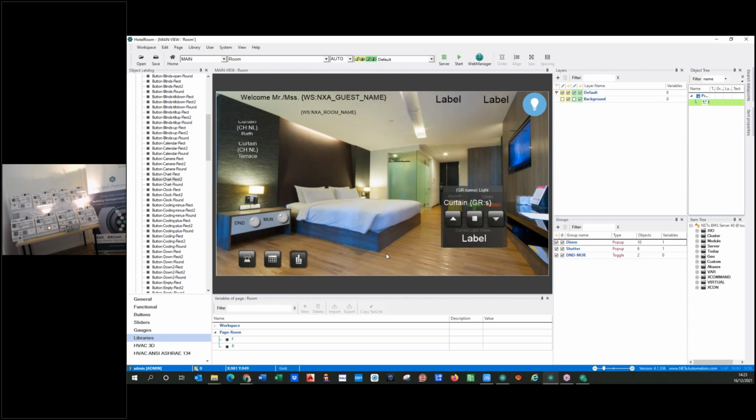But in resume, you have to think very well first how your project is and adapt your BMS to that reality. So think first in the number of circuits per room, create the most complex room, in my opinion, within the ETS, and do copies of that project, deleting circuits. That's the best advice, the best tip I can give you. So that's the fact.